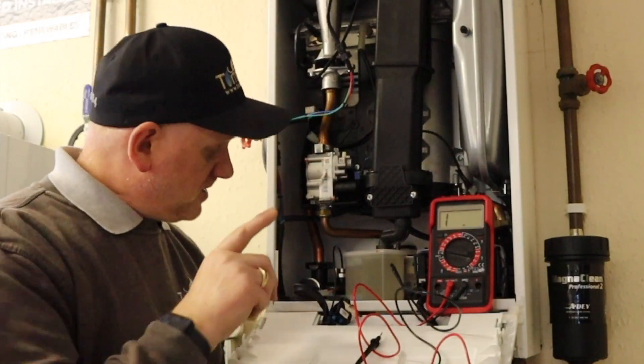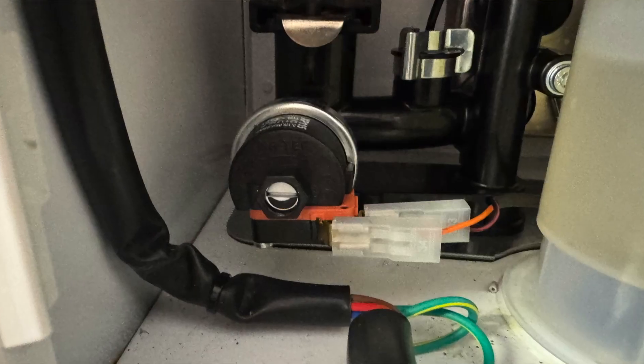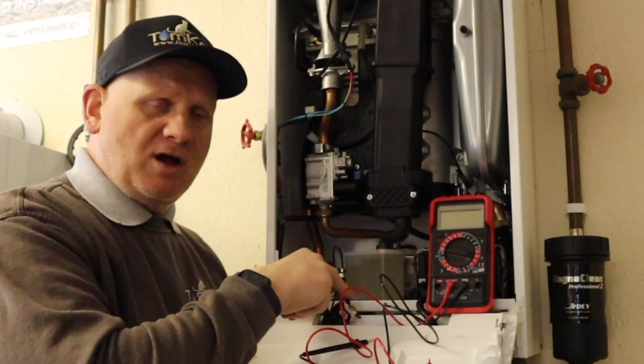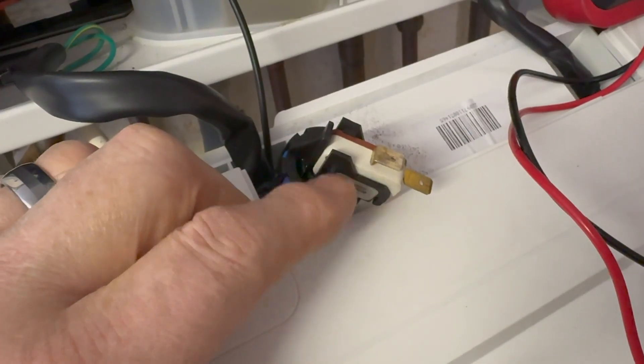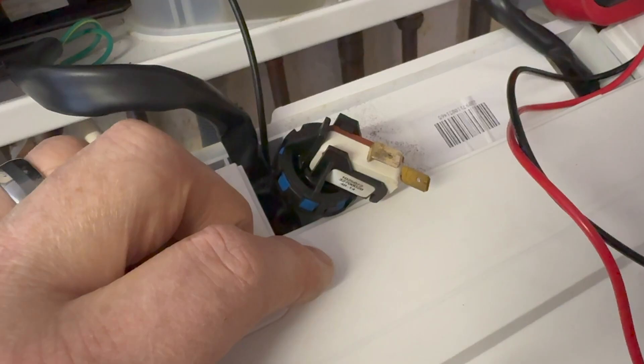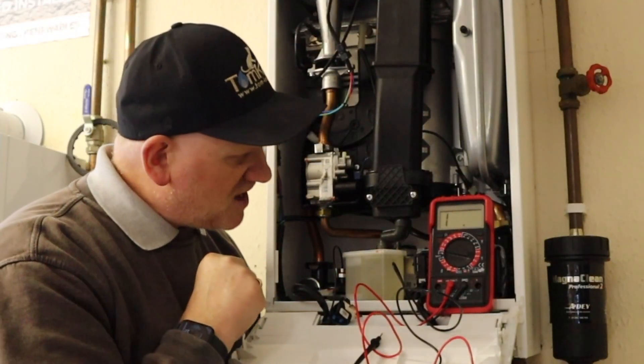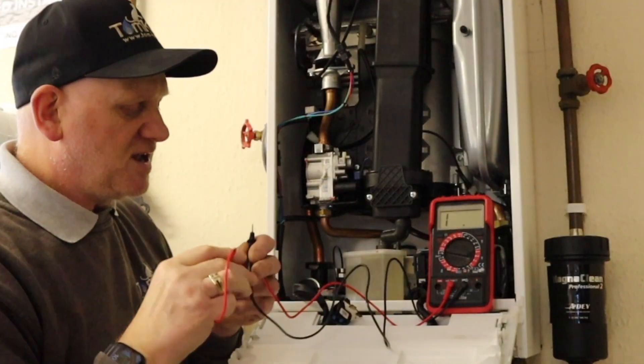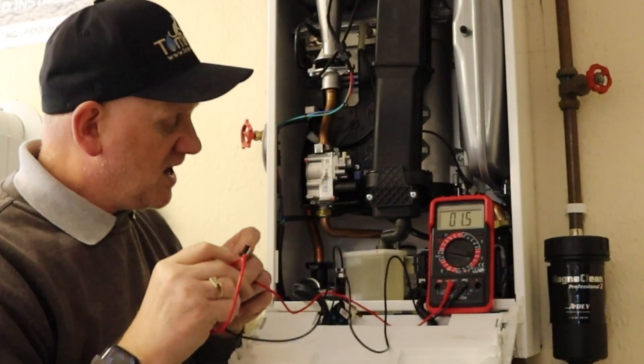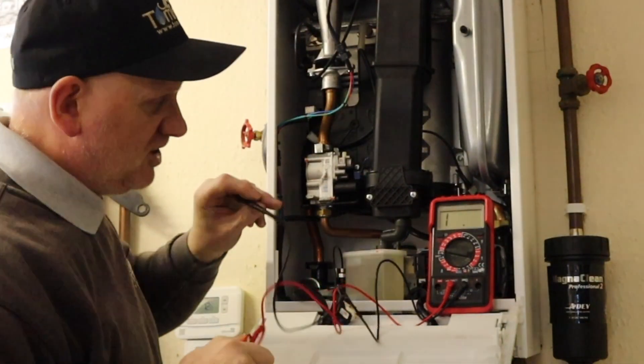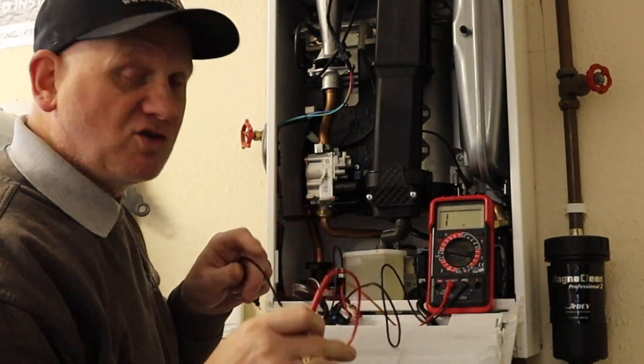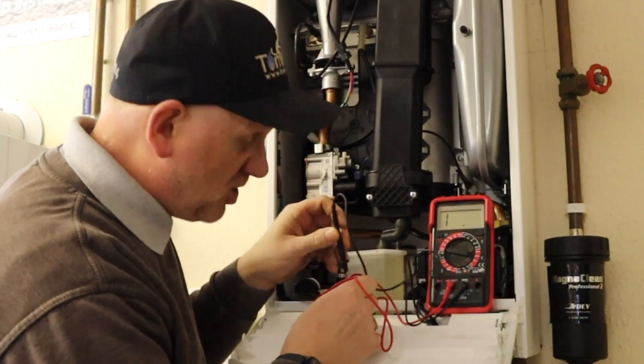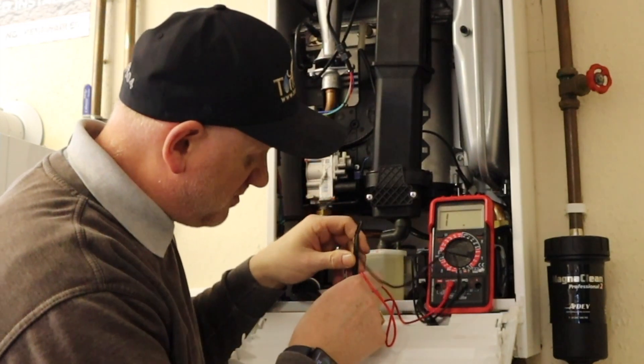Let's have a look at the switch now. Now let's take a look at this low water pressure switch on this Ideal boiler. This is out of one of the old ones, so I'll show you this one first. I've got my multimeter set up to ohms 200 ohms. So if I touch these together we're getting a buzzing. Now it's reading 1 on the screen. Yours might read OL. So if I go on to a pressure switch what isn't in the water, got no pressure in it, it's still reading 1, so there is nothing coming in or going out.